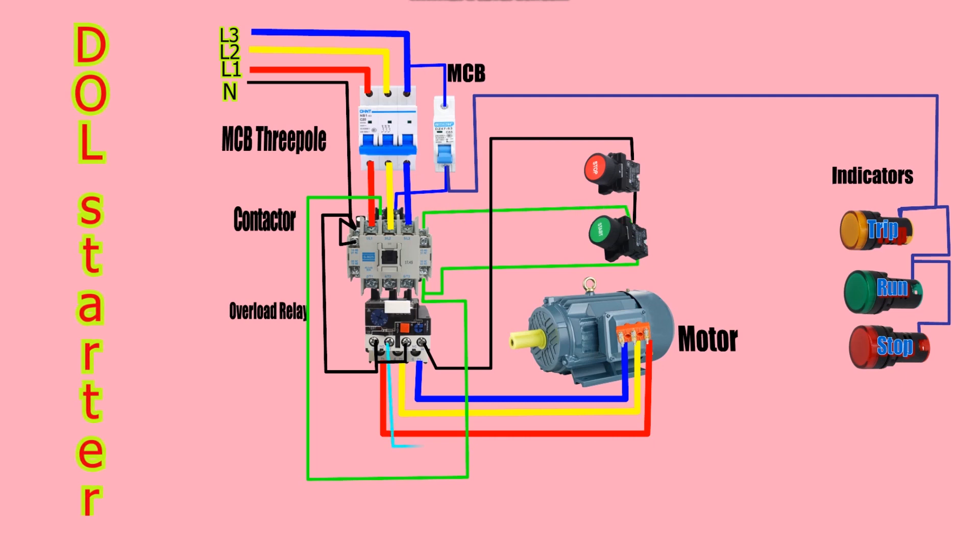As shown in the video, a light blue wire is taken from the normally open auxiliary contact of the contactor and connected to the trip indicator lamp. This light will illuminate if the overload relay trips.